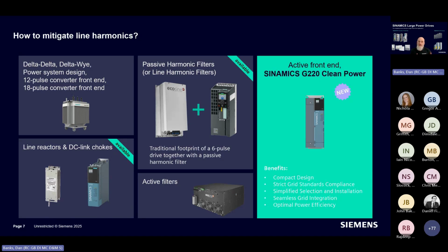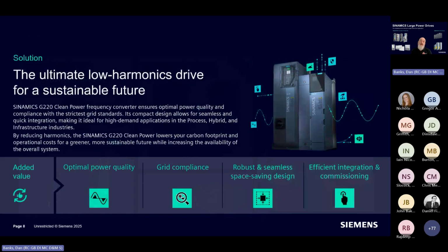And active front end drives aren't new. They've been in the marketplace for a long, long time. Traditionally used more for power regeneration, where you want to take energy from your load and put it back into your power supply, but they're also really good for keeping your harmonics down. And this is where the G220 Clean Power comes in. So this is a new drive that we've released in the last year or so, and it's using a new kind of technology to do this.